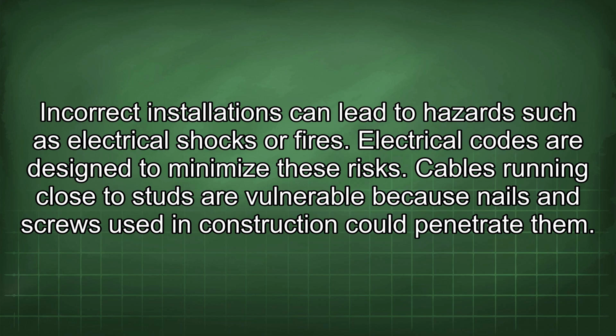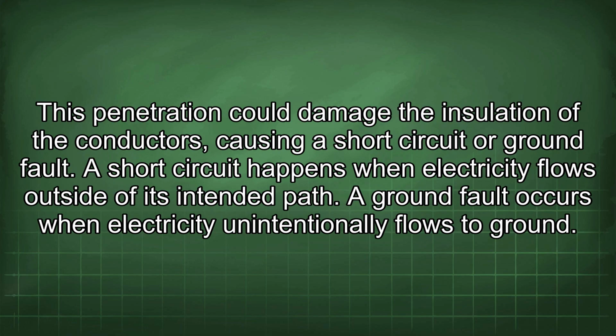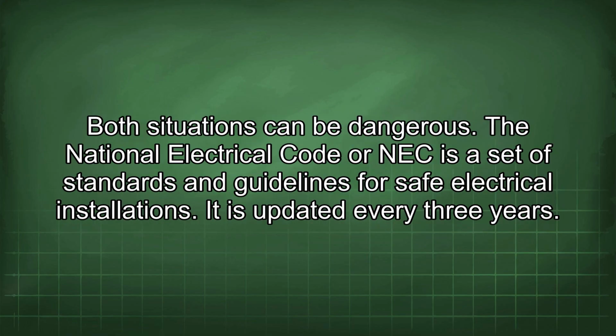Cables running close to studs are vulnerable because nails and screws used in construction could penetrate them. This penetration could damage the insulation of the conductors, causing a short circuit or ground fault. A short circuit happens when electricity flows outside of its intended path. A ground fault occurs when electricity unintentionally flows to ground. Both situations can be dangerous.